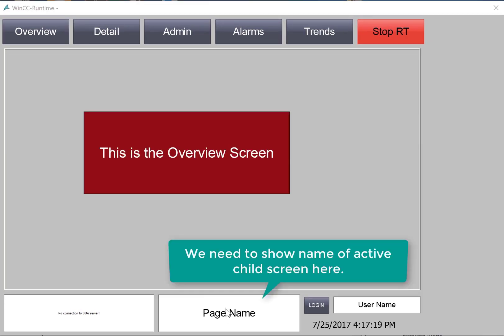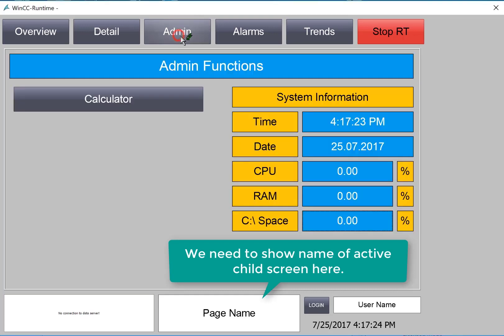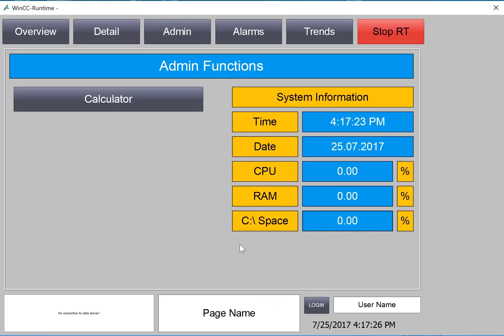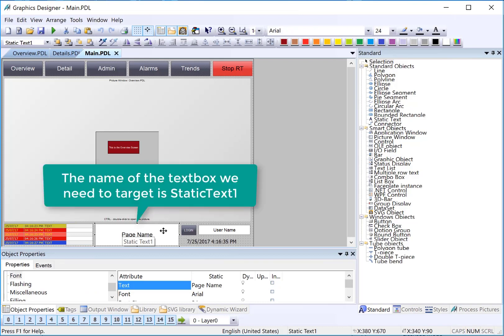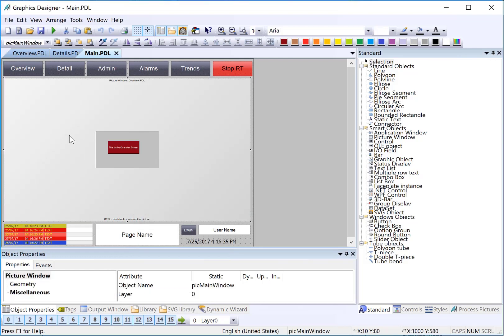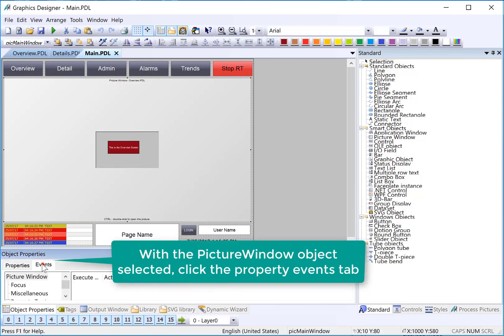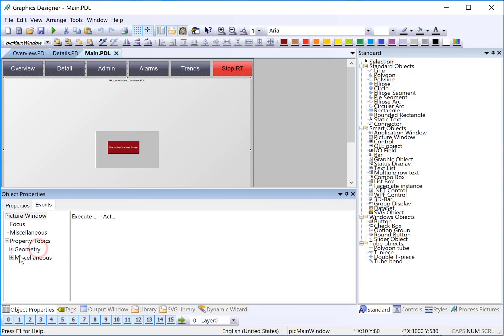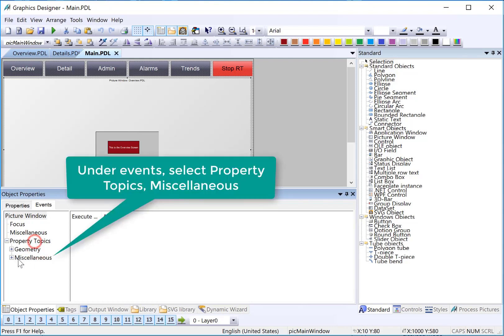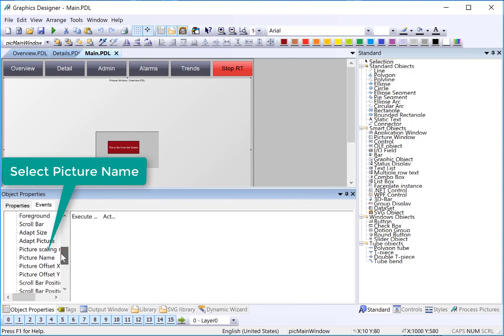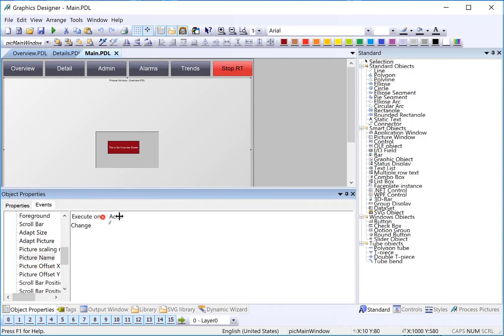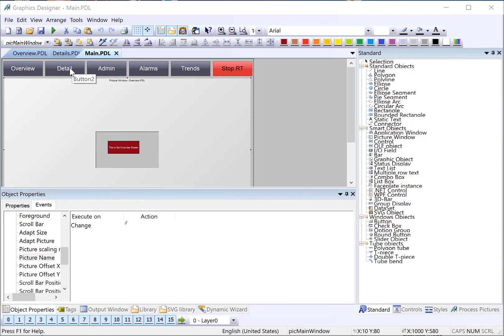The last thing we need to do in this section is to get our page name text box to update with the name of the page that we're currently viewing. Let's go back to graphics designer. This static text one down here, the text property is what needs to be updated. We're going to use a direct connect on the picture window object to accomplish updating the text here. I'm going to select the picture window object and go to events. Under property topics, miscellaneous, we see a list of the properties, and if I go to the picture name property, you can see that there is an event for that property change. Events are triggered any time a property changes. If you recall, the way that we're doing page navigation is the buttons are using Direct Connect to change the picture name property. So, this event will be generated when the picture name property changes, and we can use this to update our static text box.